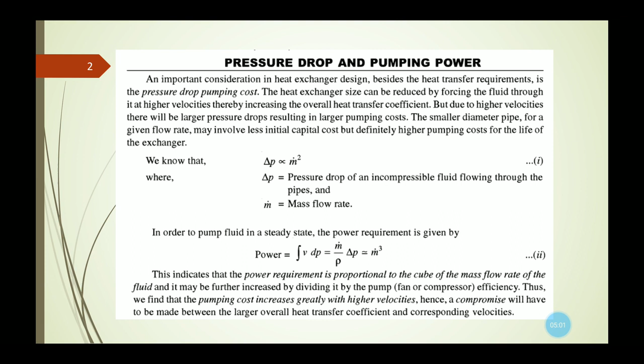So the power requirement in case of a heat exchanger is proportional to the cube of the mass flow rate of the fluid flowing through the heat exchanger. It may be further increased by dividing it by the pump efficiency. So that means the pumping cost increases greatly with higher velocities. When the fluid is flowing through the heat exchanger with higher velocities, the pumping cost increases. Hence a compromise will have to be made between the larger overall heat transfer coefficient and corresponding velocities. This we need to keep in mind while designing a heat exchanger.